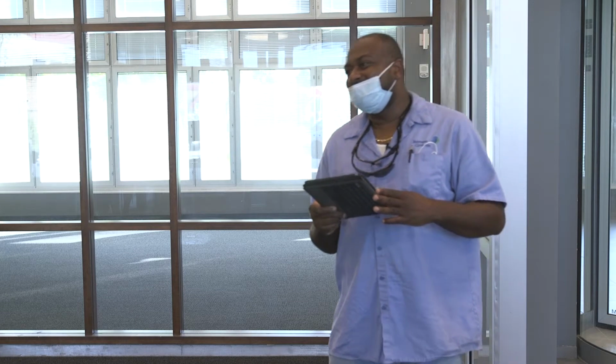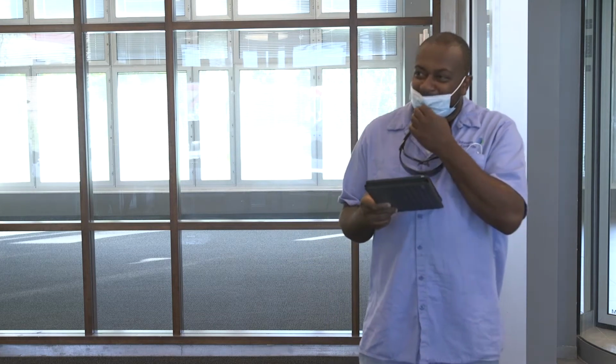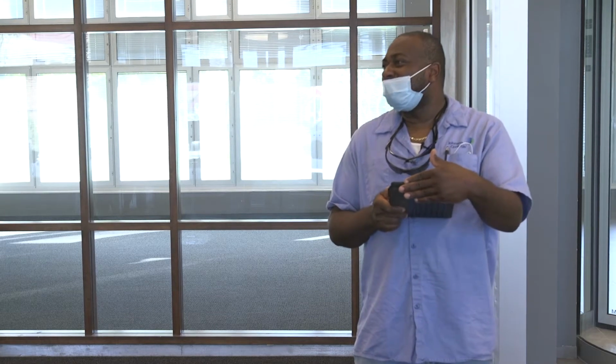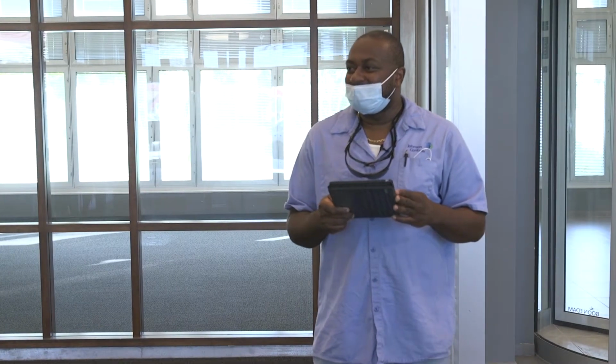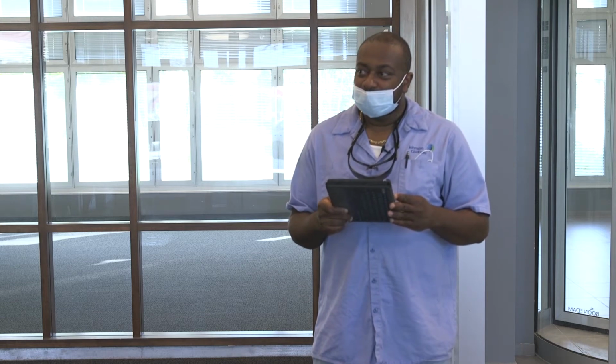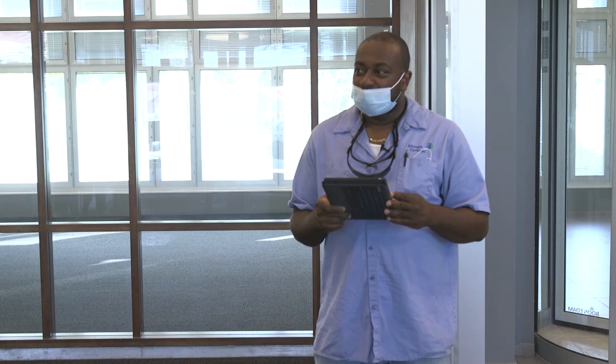Well, if a low pressure error code shows up, either you have a fan which is not putting enough air across the evaporator coil, or you have a leak in the system. But what we need to do in this case is call a technician, because we don't work with Freon here.